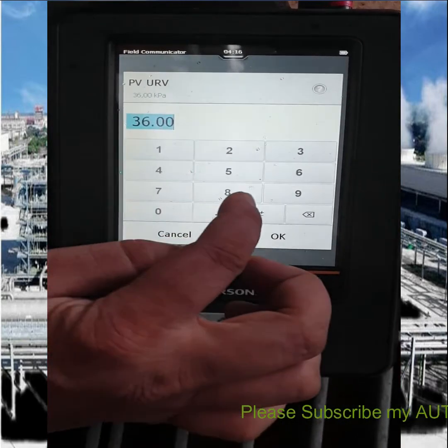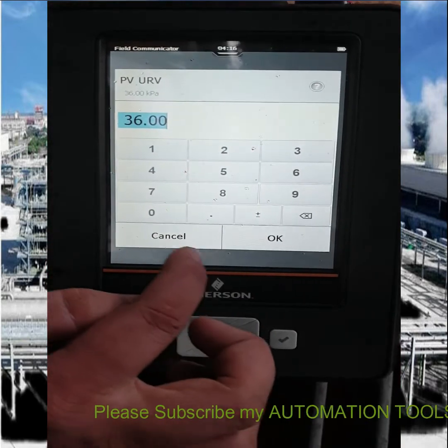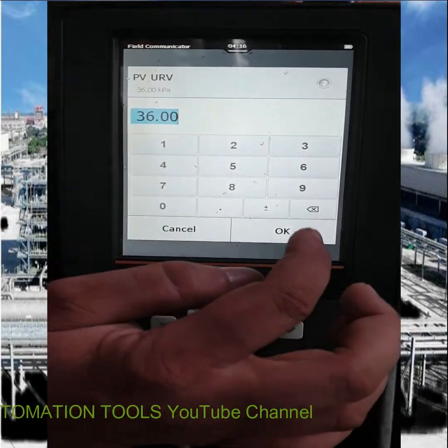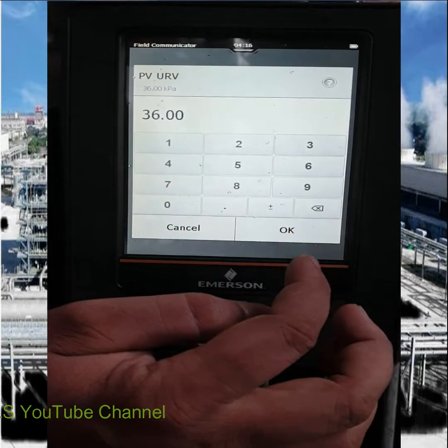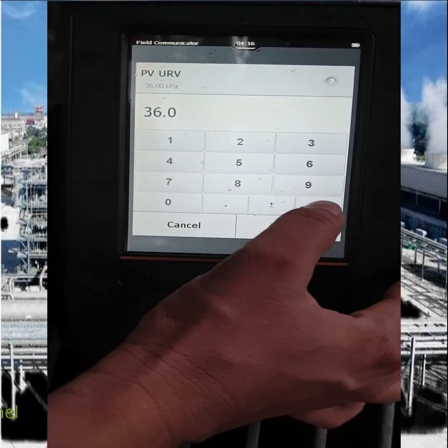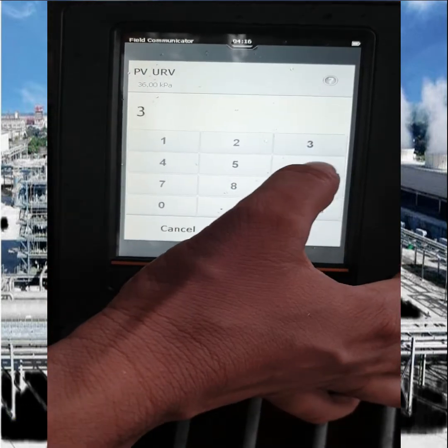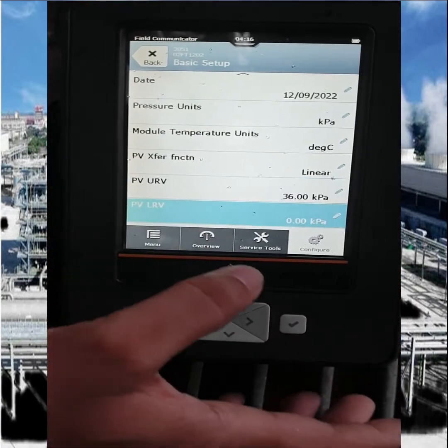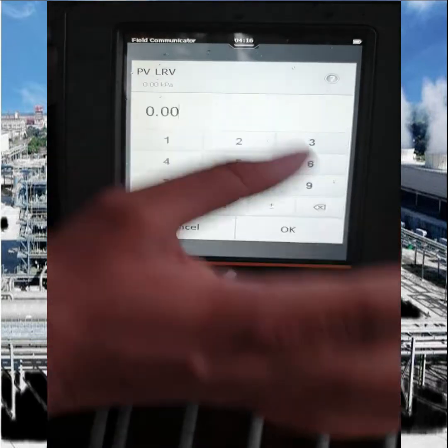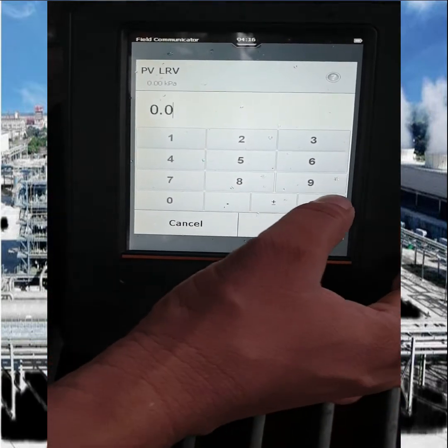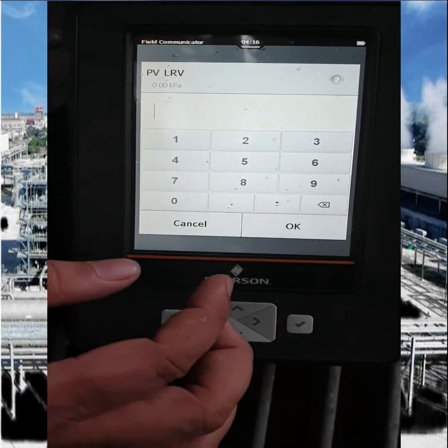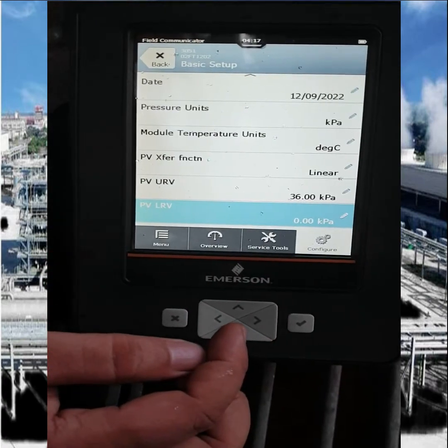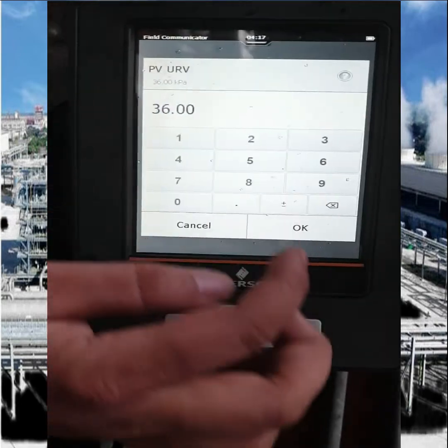From here you can change your desired upper range or lower range. Our transmitter is 0 to 36 kPa, so we select 36 and press OK for the upper range. Then go to lower range, enter the lower value and press OK. If your lower value is greater than 0 then enter that value; ours is 0 so we put 0 and press OK.